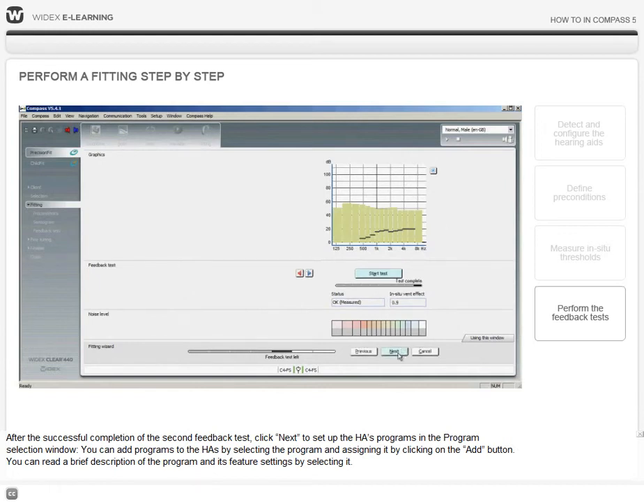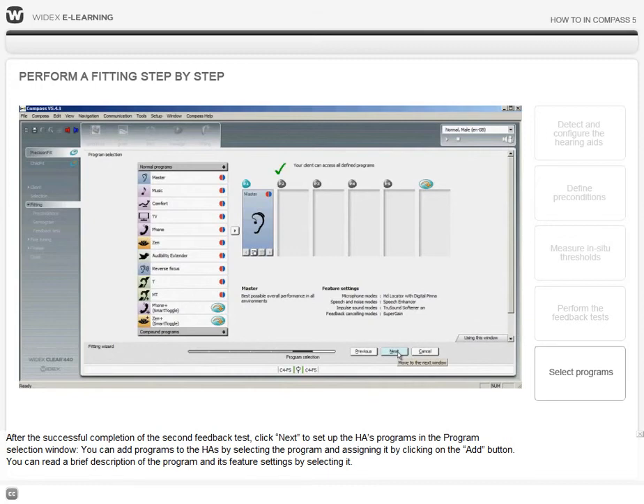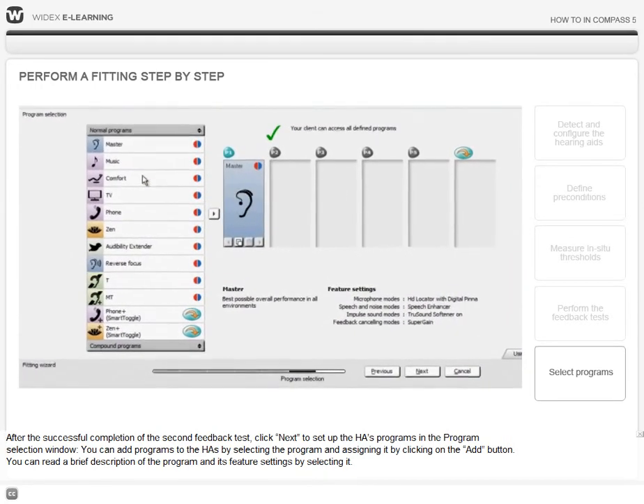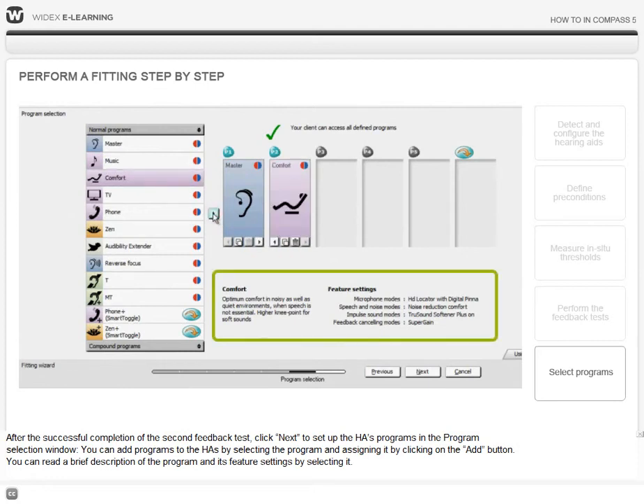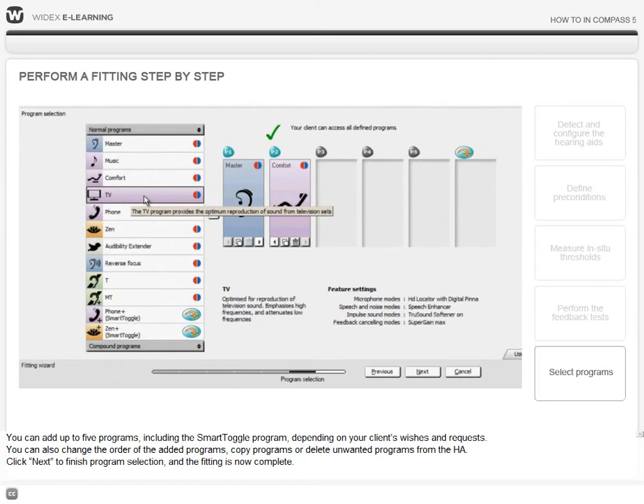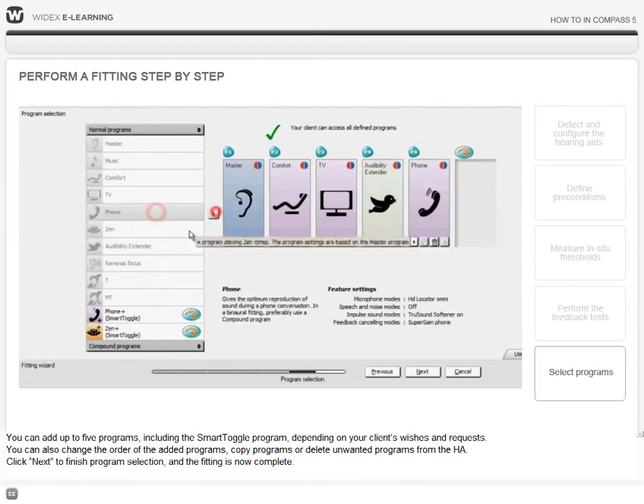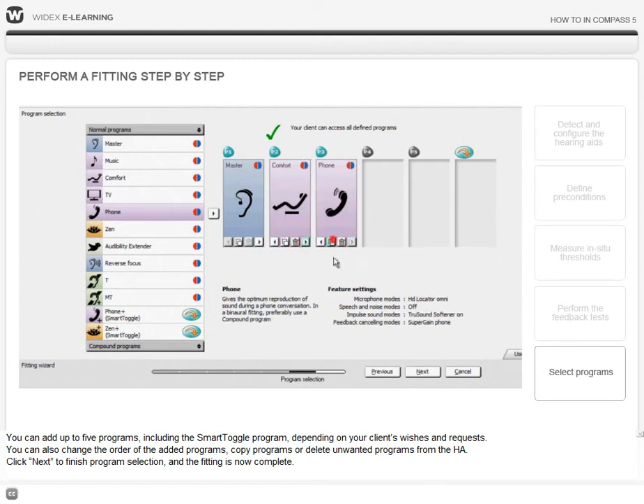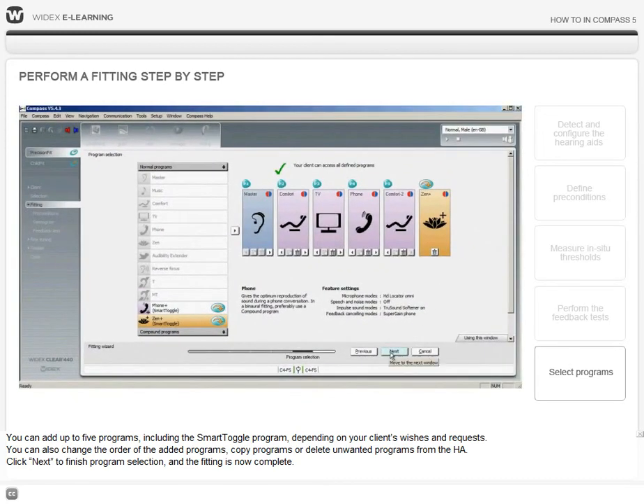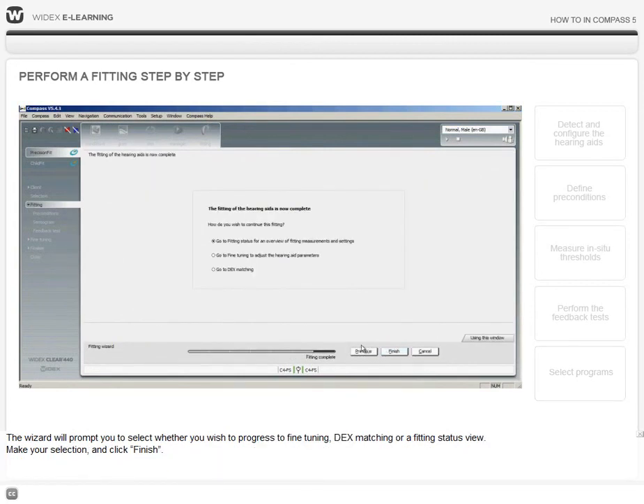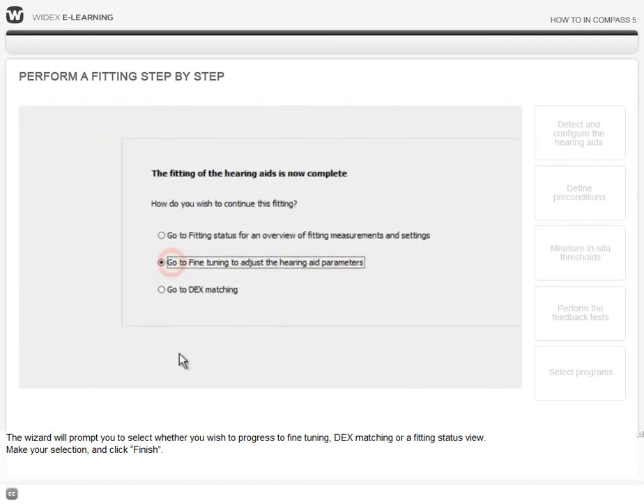After the successful completion of the second feedback test, click Next to set up the hearing aids programs in the Program Selection window. You can add programs to the hearing aids by selecting the program and assigning it by clicking on the Add button. You can read a brief description of the program and its feature settings by selecting it. You can add up to 5 programs, including the Smart Toggle program, depending on your client's wishes and requests. You can also change the order of the added programs, copy programs, or delete unwanted programs from the hearing aids. Click Next to finish program selection, and the fitting is now complete. The wizard will prompt you to select whether you wish to progress to fine-tuning, DEX matching, or a fitting status view. Make your selection and click Finish.